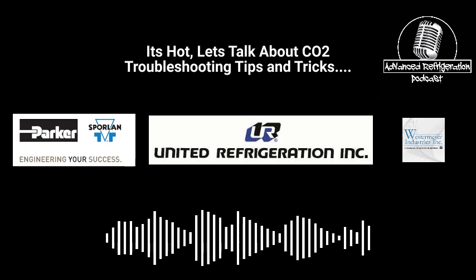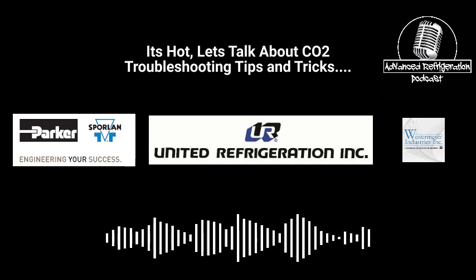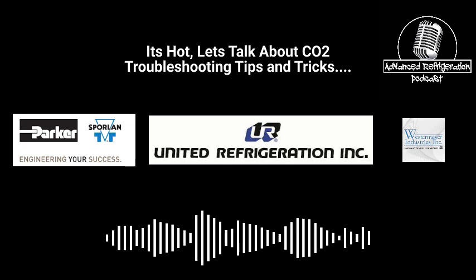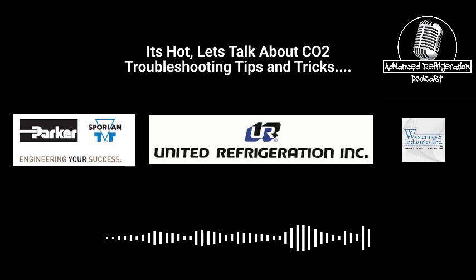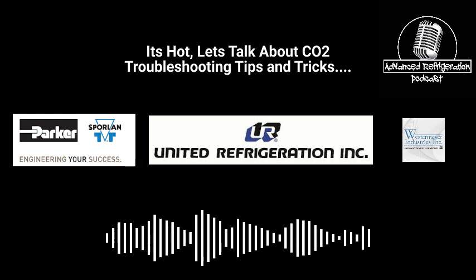Yeah. So you've got two things. If you're at 100%, and you're not running all the compressors, generally the valve's messed up. Say that one more time. If U24 is at 100% and it's whistling through there, and you're not running almost 100% capacity on the medium temp, then the valve is messed up. Because if the valve was truly at 100%, it would be sending so much vapor to the medium temp that it would load the rack up. So it would load up the medium temp compressors.